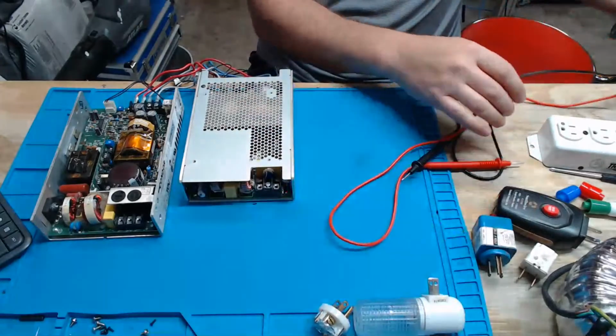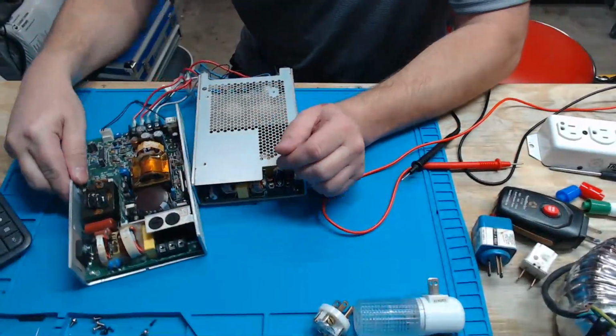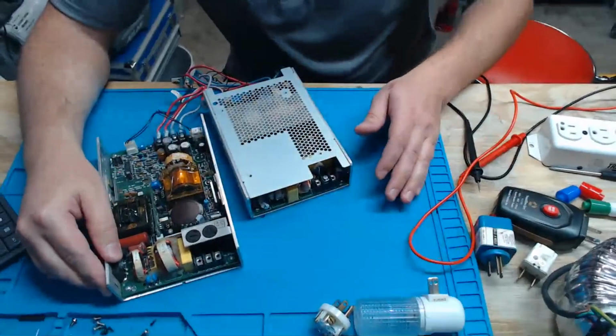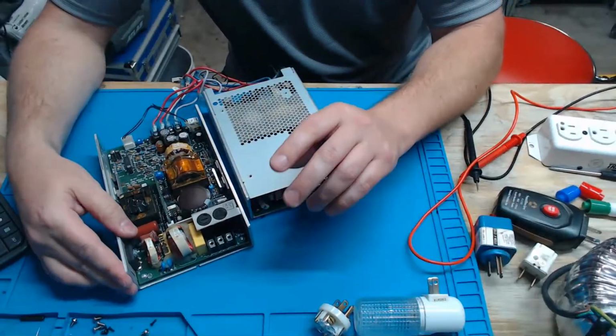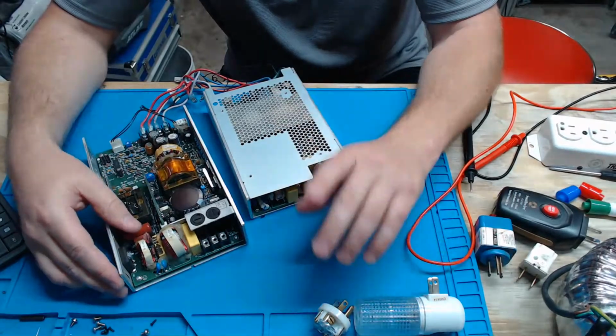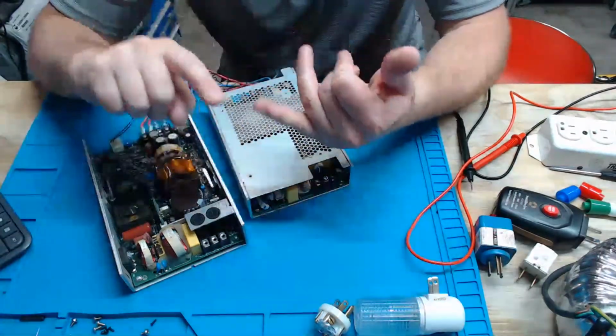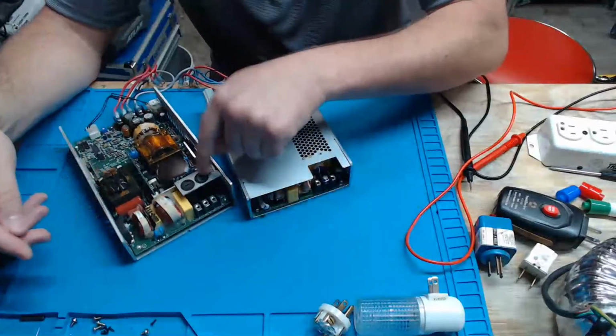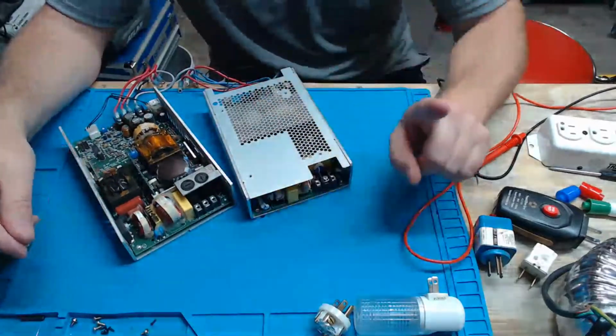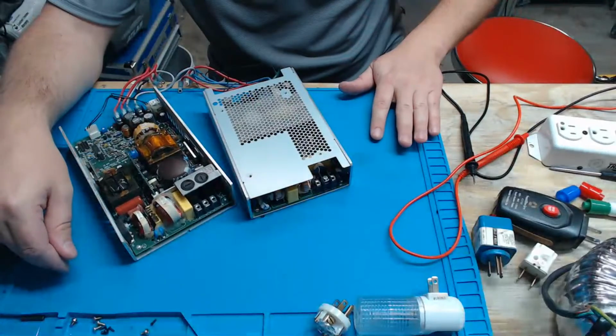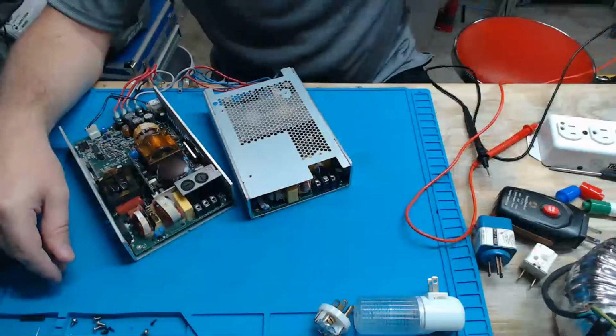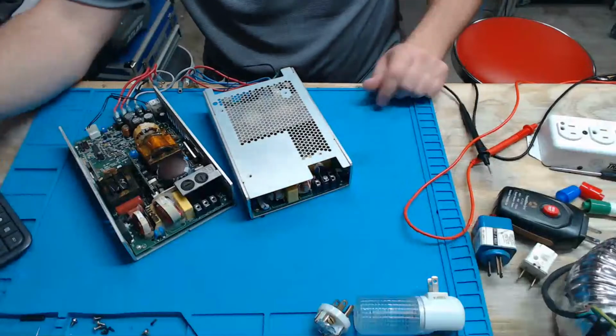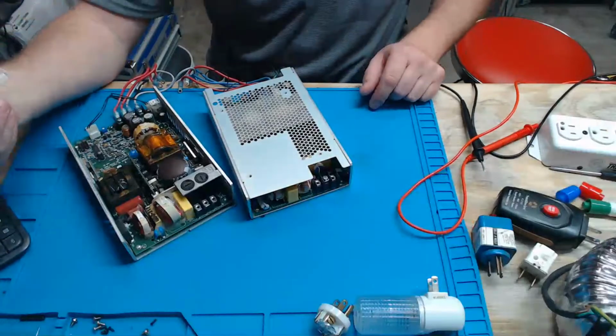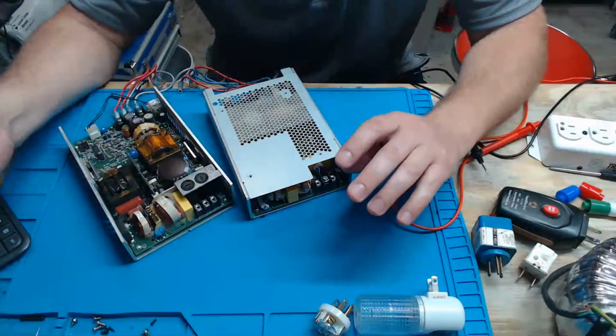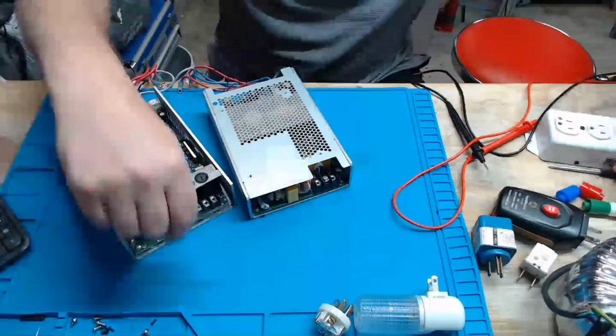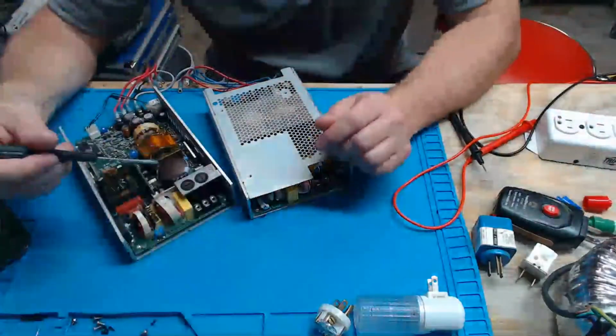Okay, that's very, very important because that is going to bring us into medical equipment, specifically medical devices that are probably going to be in and about a wet location or an operating room, right? And that is what we have right here. These are medical grade power supplies, and one of the easiest ways to figure out if something is a medical grade power supply is try and buy it. Because believe it or not, medical grade power supplies are some of the hardest things to get because manufacturers almost never want to sell them to anybody.